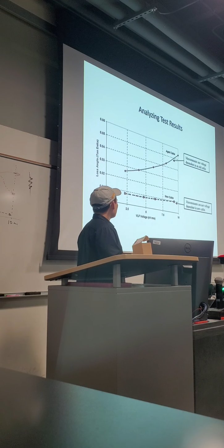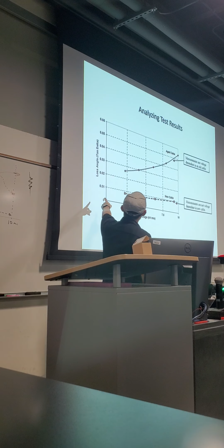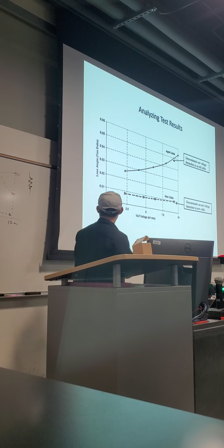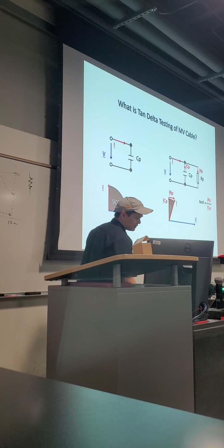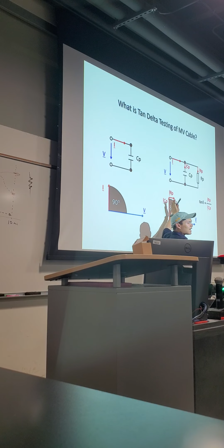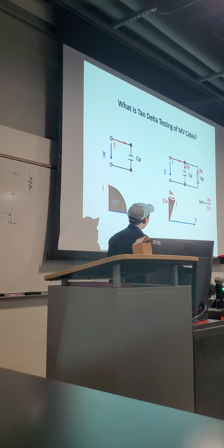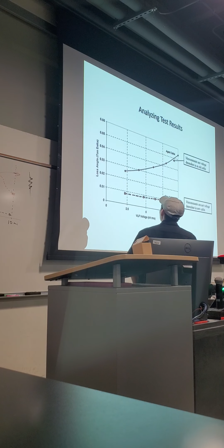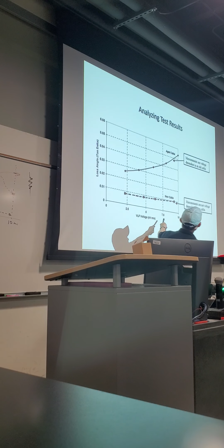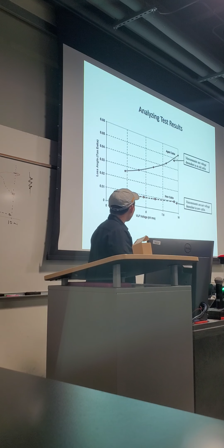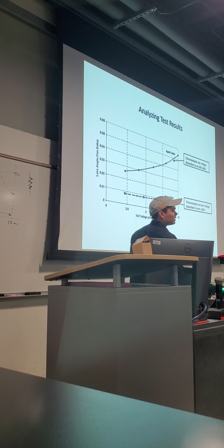Yeah, pretty stable, very stable, right? And again, this value is almost zero in terms of that loss angle. Zero angle just means that if this is zero, then this I is exactly equivalent to your I_CP. But as this angle gets bigger, which we're seeing for aged cable, that angle will continually increase, especially as you step up in voltage. So we see that measurements are voltage dependent in old cable, whereas with new cable they are not.